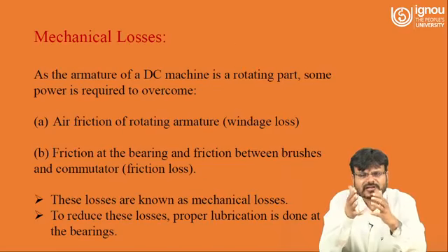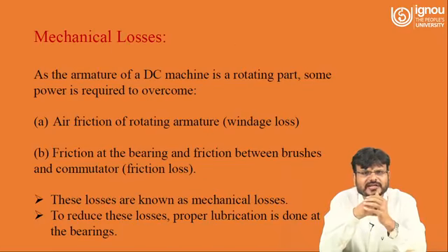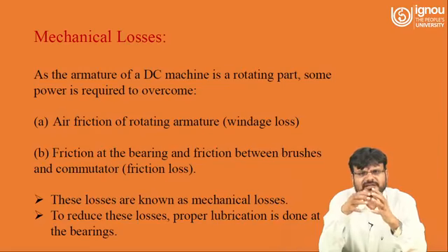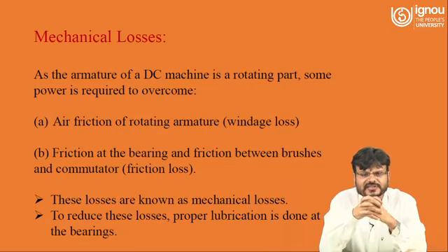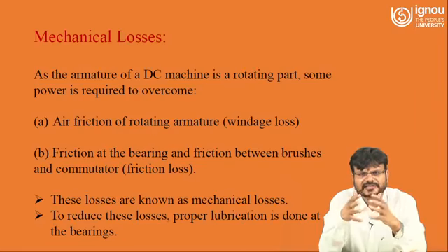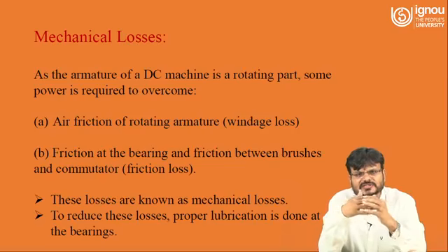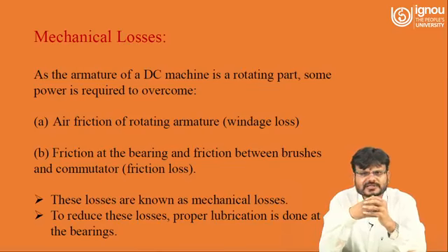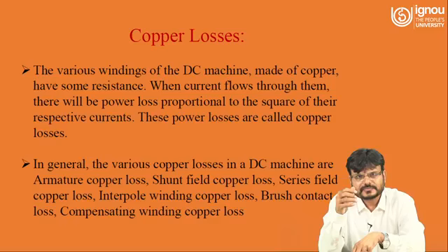Now another loss that I have already told you, mechanical losses, can be classified as air frictional losses, frictional losses at the bearing, and the friction between the brushes and the commutator. These losses are known as the mechanical losses, and to reduce these losses, proper lubrication is done at the bearing.